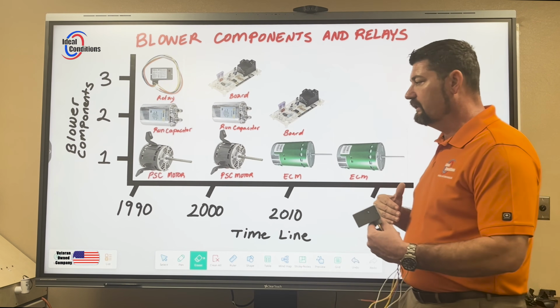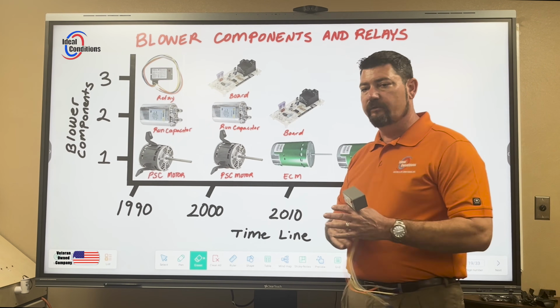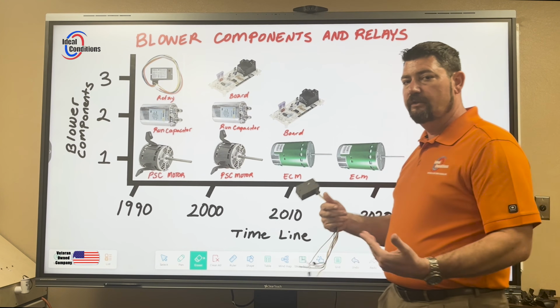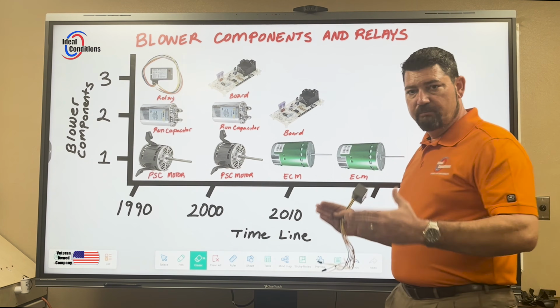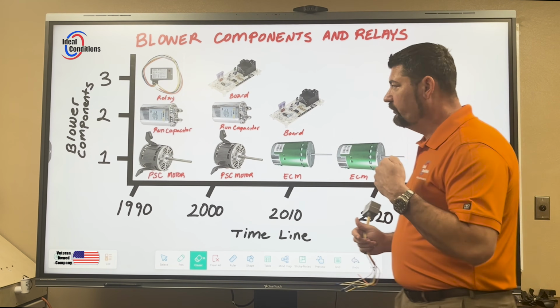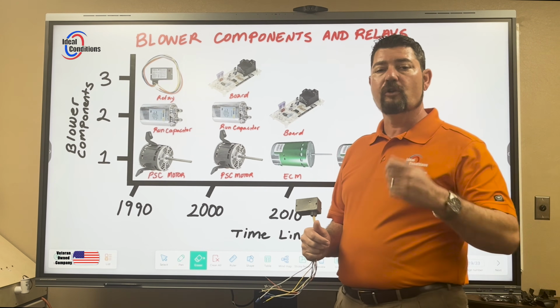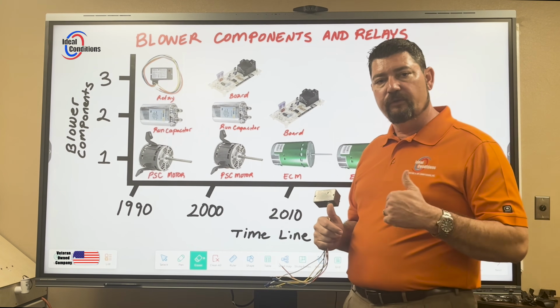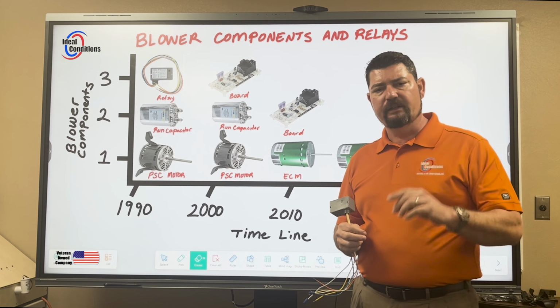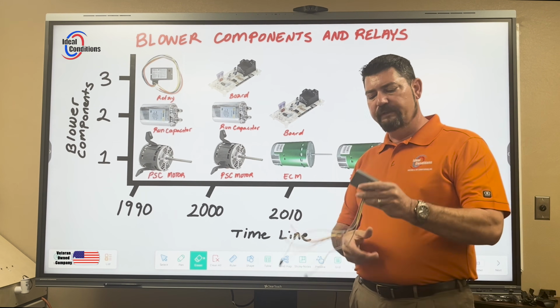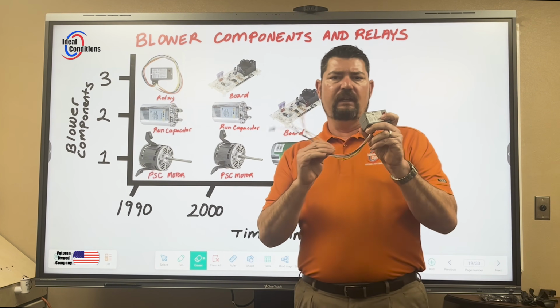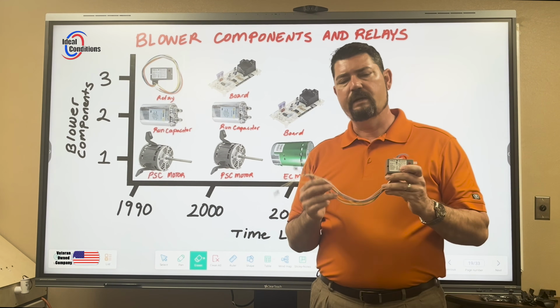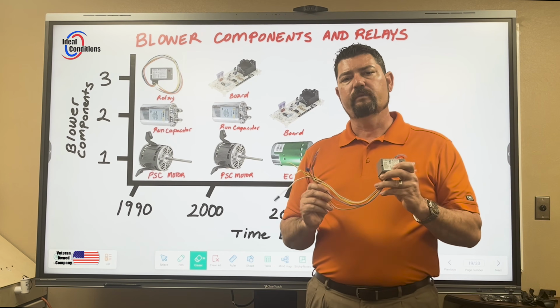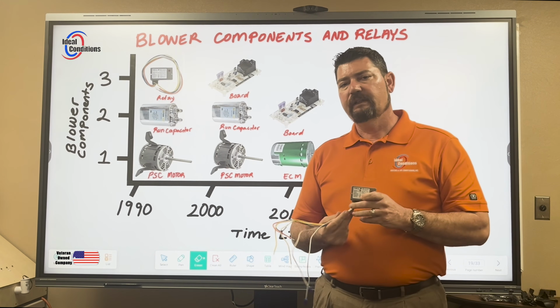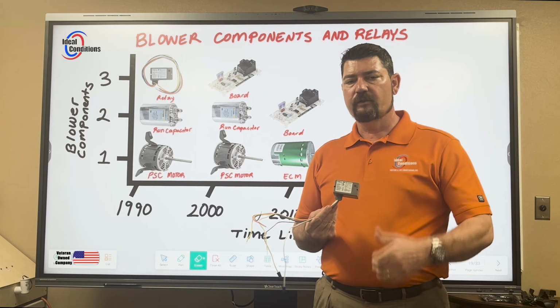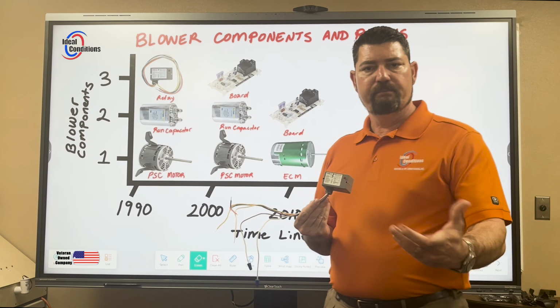A lot of these videos, it's a lot of different varieties of relays and control boards that we're going to introduce, so we can go over in as much depth as possible. We try to introduce extra loads because there are other terminals there, and we don't want you to look at those relays and say, hey, I don't need that because those extra terminals we're not using. I don't need this relay because I don't have anything that's direct current. I don't have anything that's 120 coil. I don't have anything that I need for normally closed. Why can't you just use this relay for what you need it for? Cap off the other wires, use your normally open contact side, and put 24 volts on it.